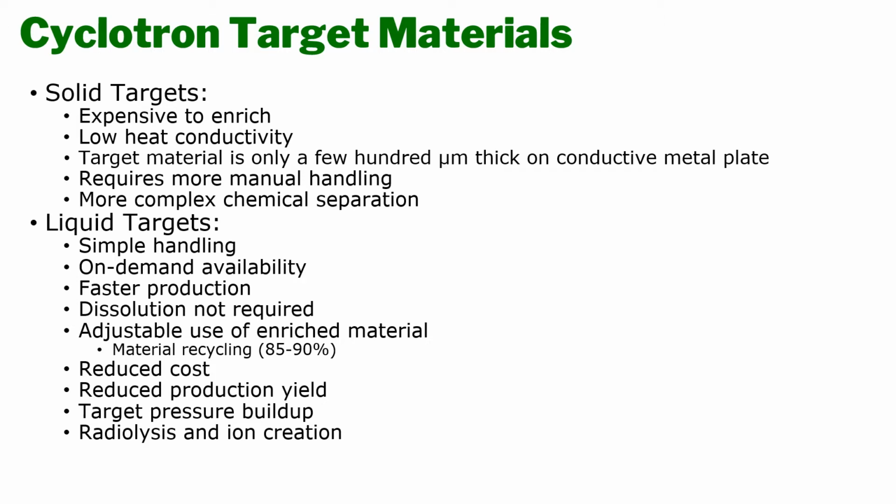However, there are a few drawbacks as well. Overall yield of production is lower than that of solid targets as the solution absorbs some of the beam, creating issues with radiolysis, producing gases and undesirable ions within the solution. These gases produced increase the pressure within the target container that has to be addressed as well.